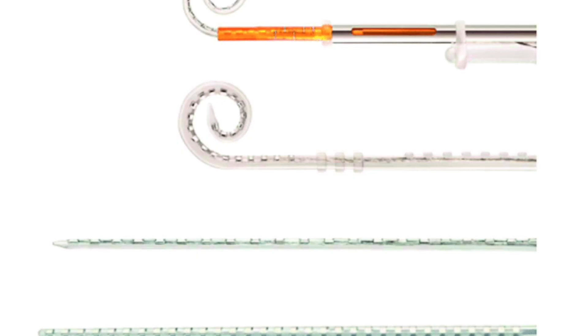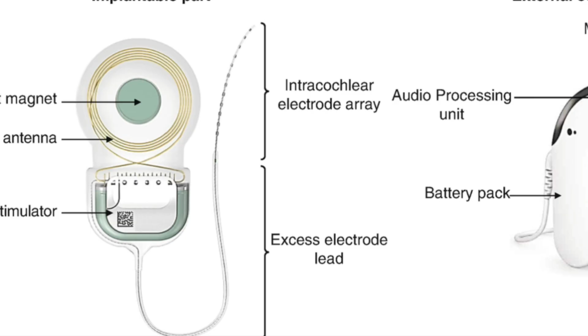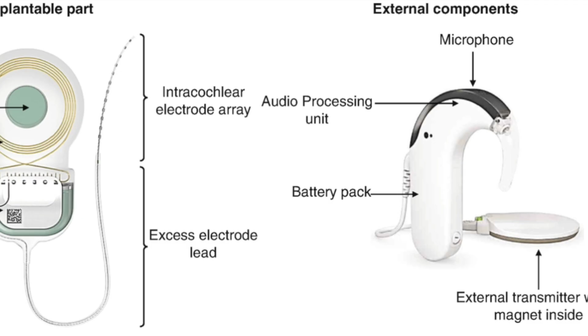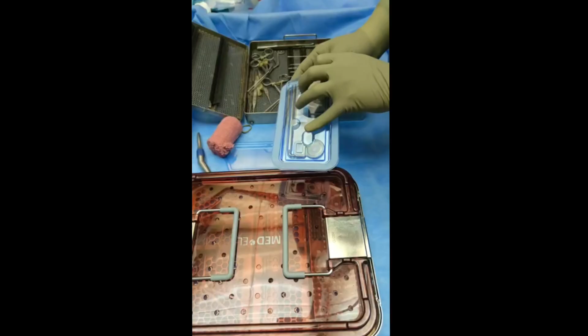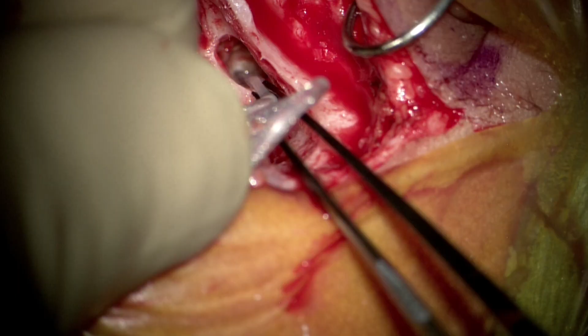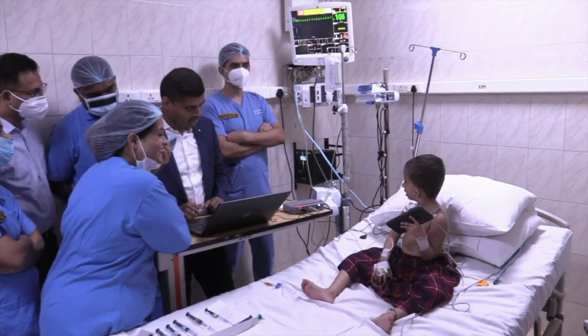A CI converts sound into an electrical current that stimulates the auditory nerve and produces the sensation of sound for the recipient. The mechanical function of the ear is bypassed as the signal directly reaches the auditory nerve. A CI consists of external and internal parts. Microphone, speech processor, and transmitting coil are located externally. The receiver stimulator is implanted in the mastoid bone behind the ear, and the electrode array is implanted into the cochlea. The device is switched on in the post-operative period, programmed, and the recipient undergoes training and rehabilitation to learn to use auditory cues obtained from the device. Cochlear implantation leads to significant and rapid improvement in speech perception and speech production, and more gradual but progressive improvement in complex language and grammar in most cases.